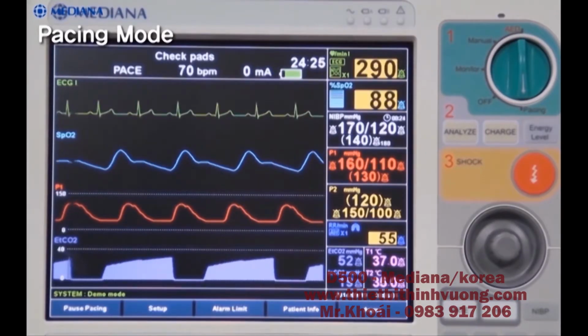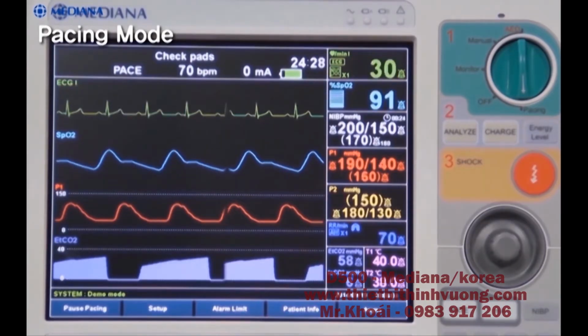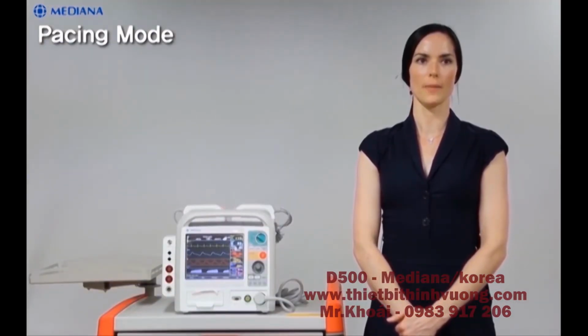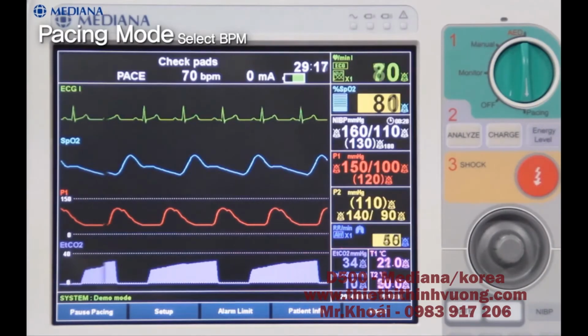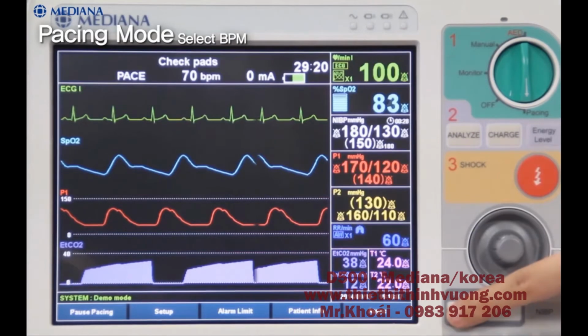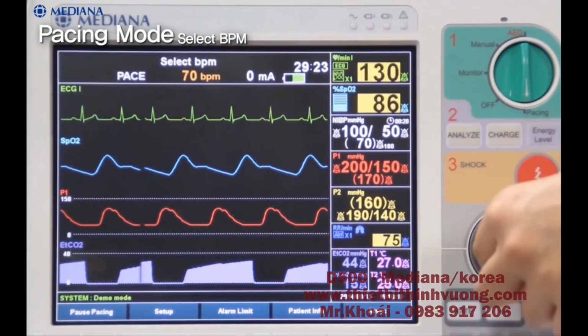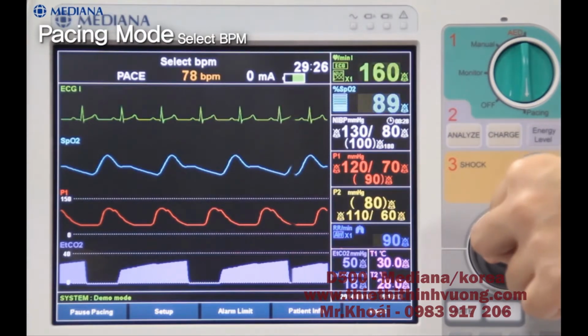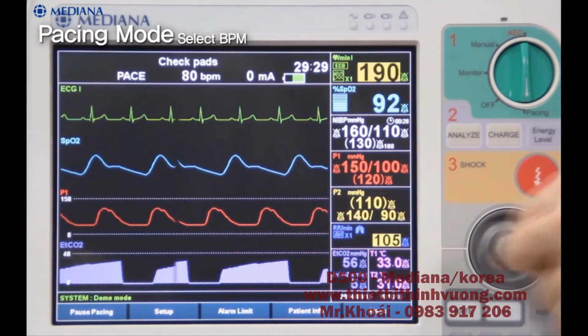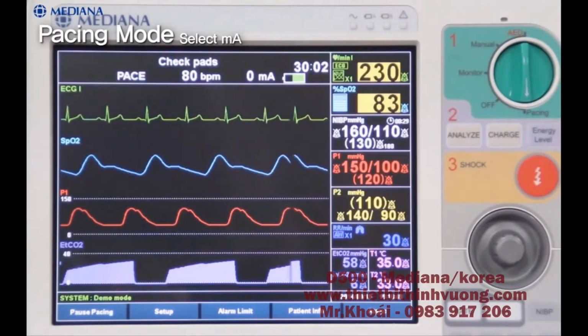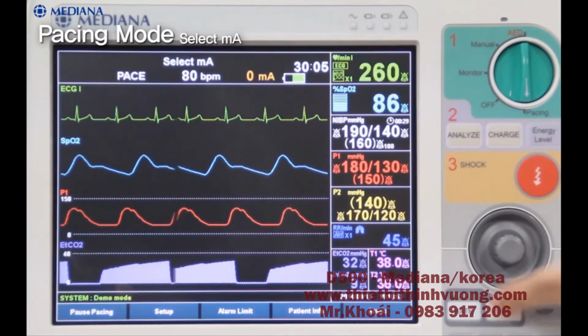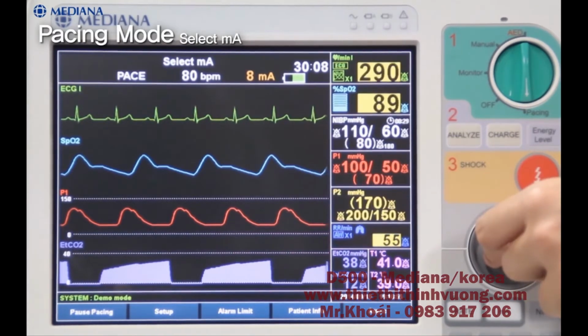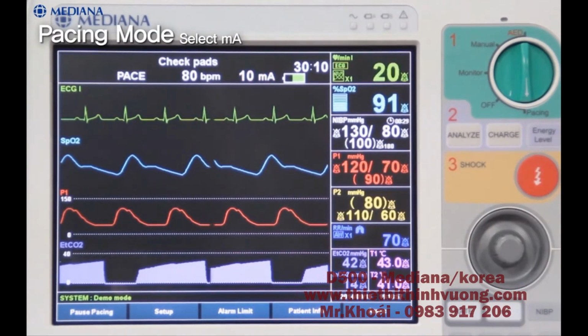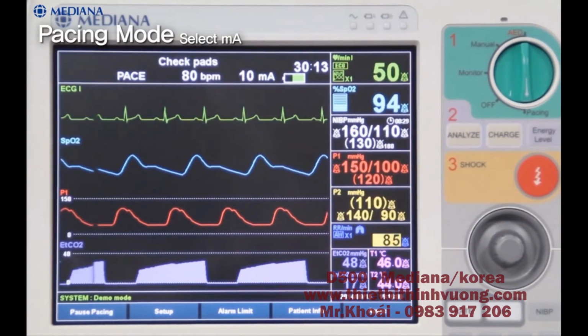on the top of the screen, and other parameter information will be displayed. When the rate button is pressed, the color of the pulse rate value changes and can be modified. Select BPM is displayed, and by pressing and rotating the multi-function knob, you can select the desired value of the pacing pulse. The value is changed by 2 beats per minute. When the milliampere button is pressed, the color of the output value changes and the output value can be modified. The select milliampere message is displayed, and by pressing and rotating the multifunction knob, you select the desired output value. The value is changed by 2 milliampere.